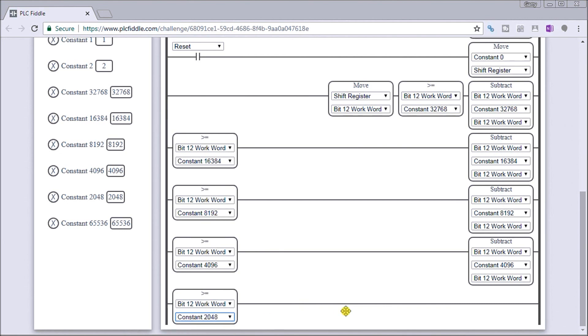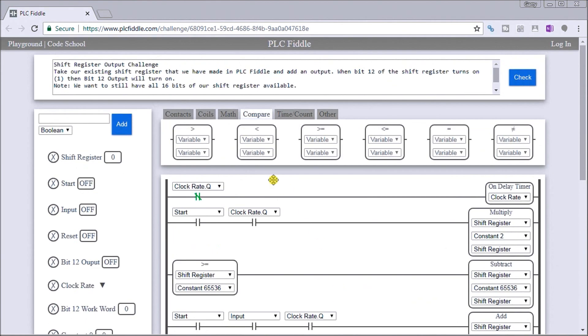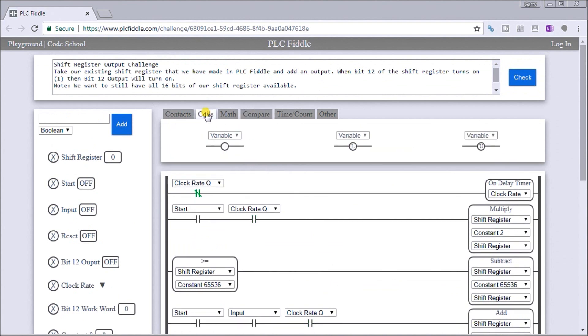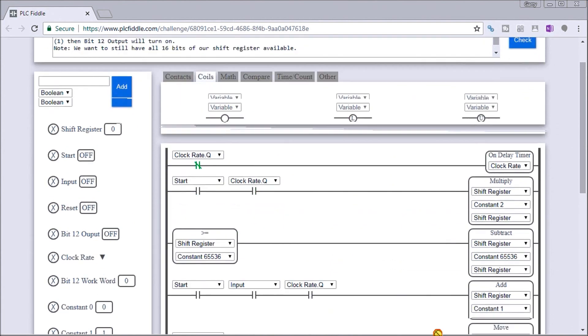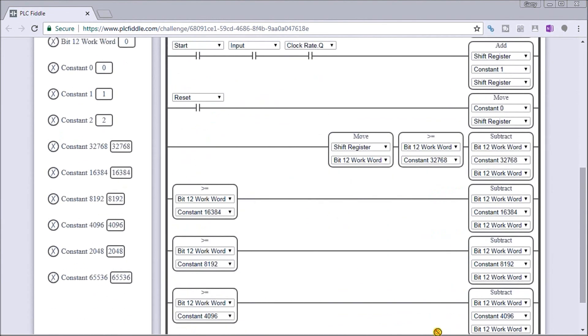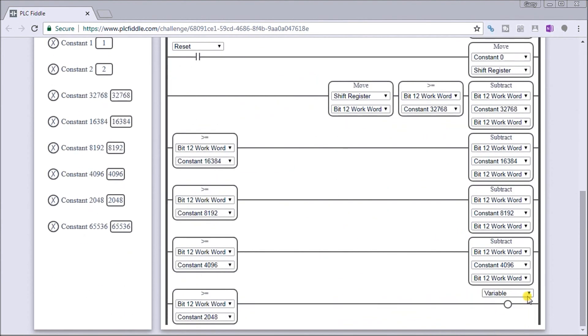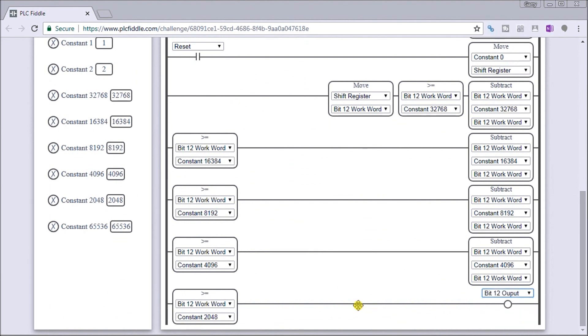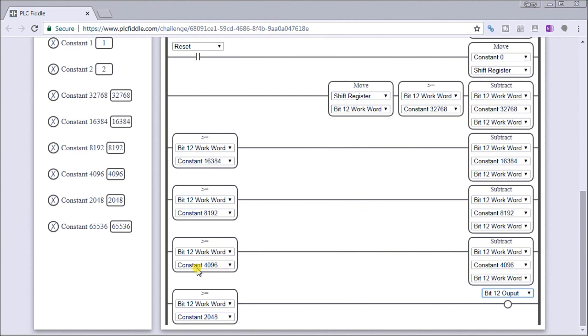And what we need now is our bit 12 output. So just to summarize, we take the shift register, we put it in there as our work word, and then we can manipulate bit 12 work word around by masking out the first four bits before bit 12 that I want to look at. So I subtract these constants from it if they're on or greater than, which leads me to say that if bit 12 work word is greater than 2,048, I turn on my bit 12 here.